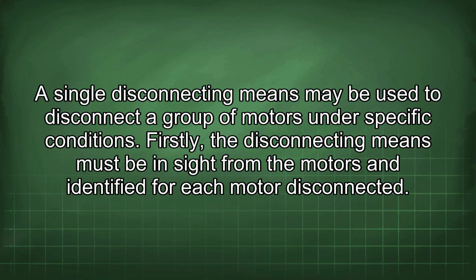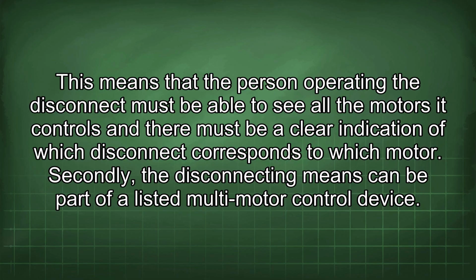A single disconnecting means may be used to disconnect a group of motors under specific conditions. Firstly, the disconnecting means must be in sight from the motors and identified for each motor disconnected. This means that the person operating the disconnect must be able to see all the motors it controls, and there must be a clear indication of which disconnect corresponds to which motor.